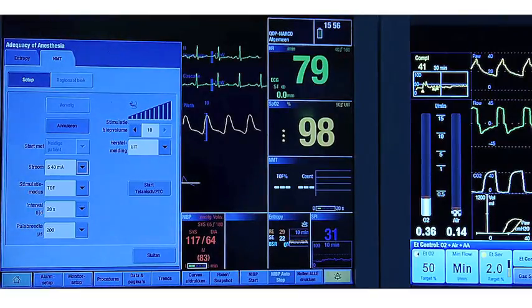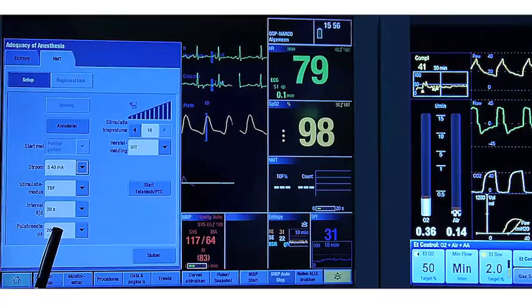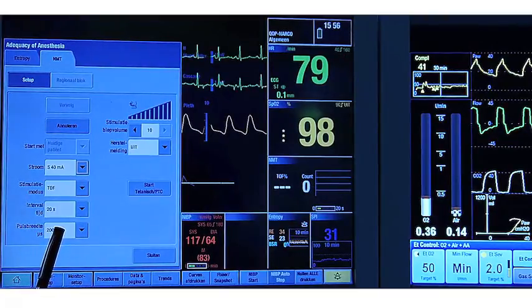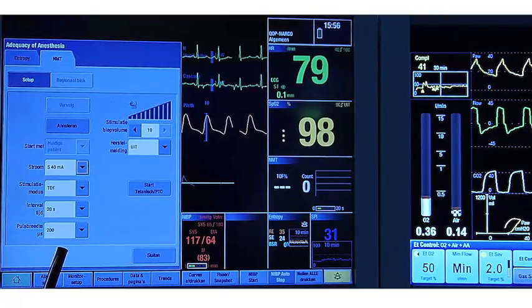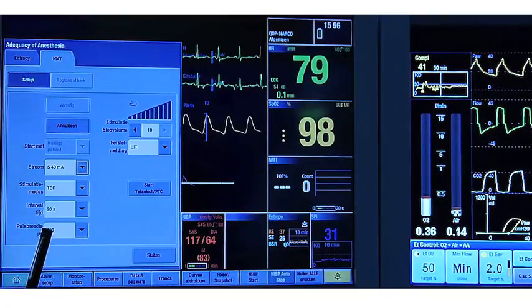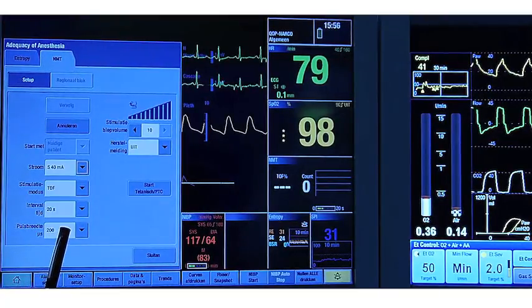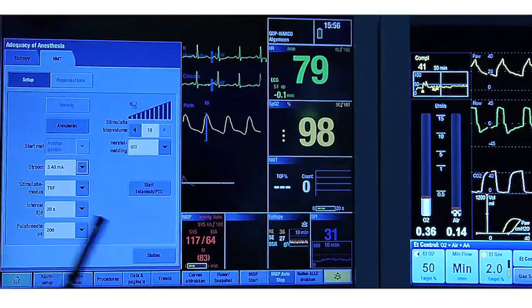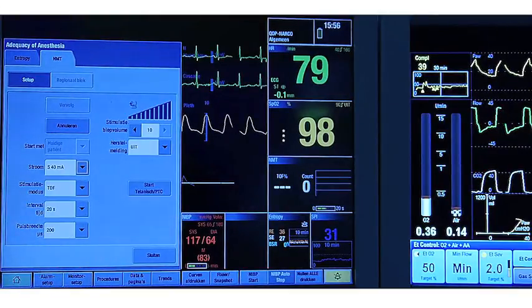Most of the time, 200 microseconds is sufficient. Exceptionally in obese patients, you need to go to 300. You have to do it at the calibration phase, or in infants to go to 100, what you also have to do at calibration.